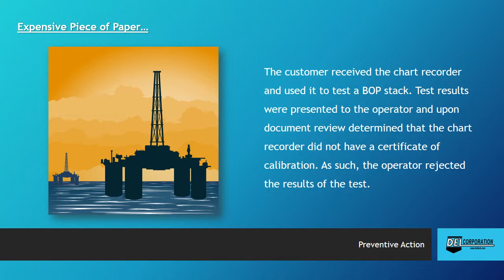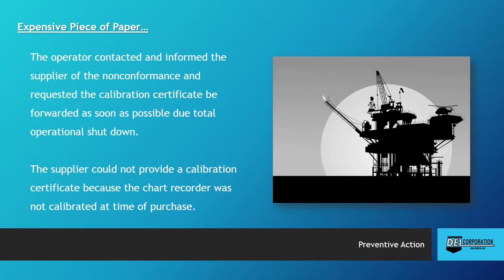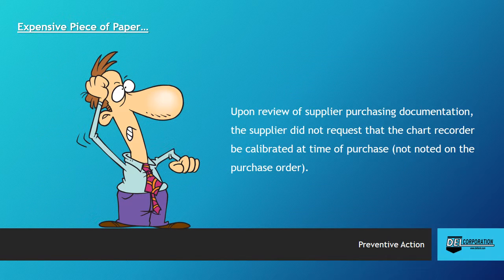The customer received the chart recorder and used it to test a BOP stack. Test results were presented to the operator, and upon documentation review, determined that the chart recorder did not have a certificate of calibration. As such, the operator rejected the results of the test. The operator contacted and informed the supplier of the nonconformance and requested the calibration certificate be forwarded as soon as possible due to total operational shutdown. The supplier could not provide a calibration certificate because the chart recorder was not calibrated at time of purchase. Upon review of supplier purchasing documentation, the supplier did not request that the chart recorder be calibrated at time of purchase, not noted on the purchase order.